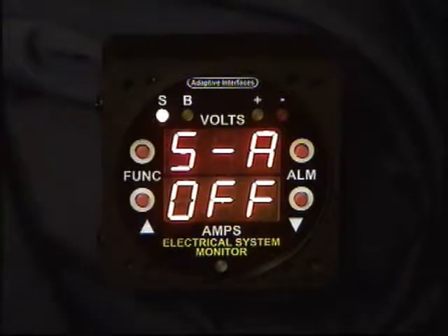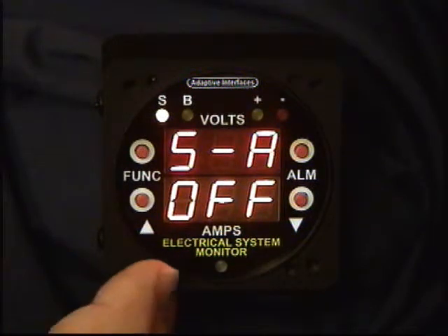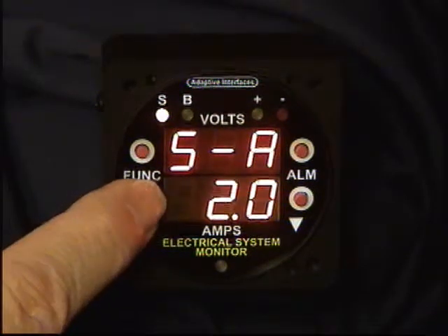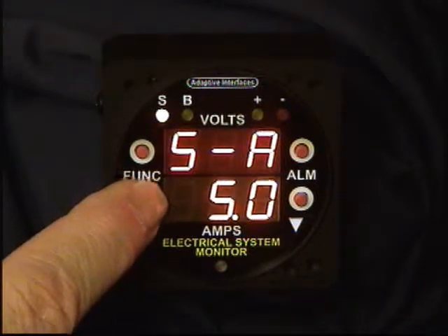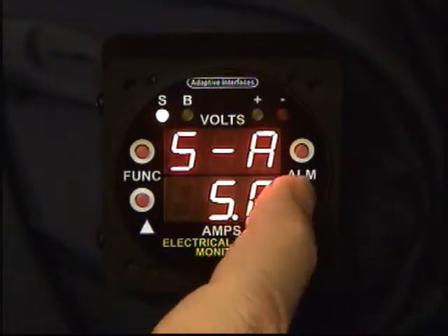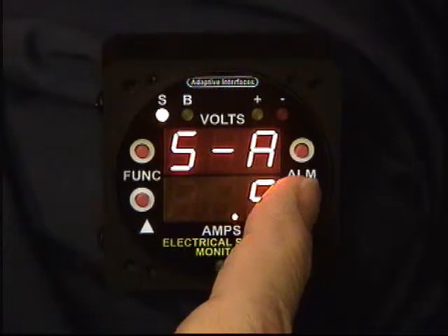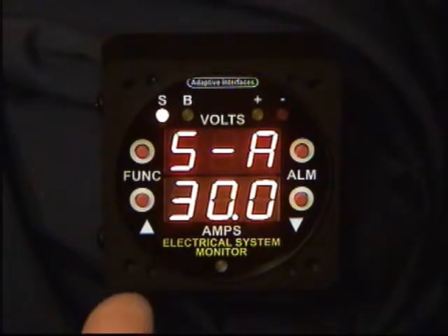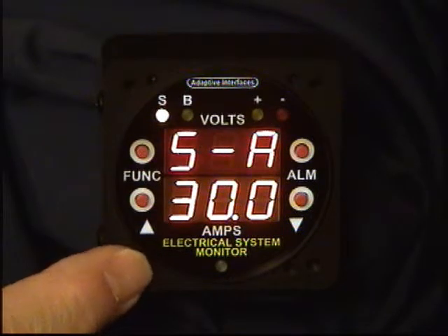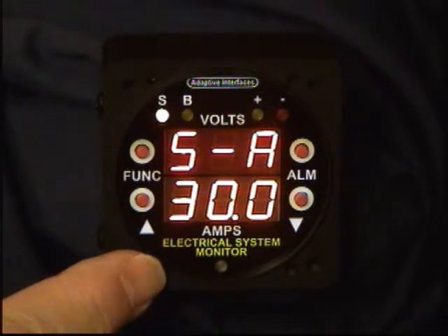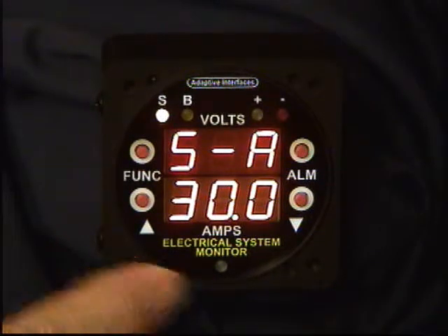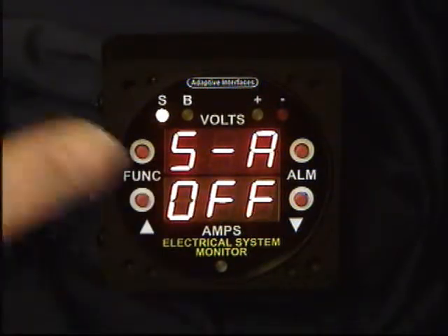The next function is a current alarm level for the system current sensor. Right now it's turned off, but it can be selected in half amp increments. If we go back down through the functions, it can go all the way from 0 to 30 amperes. In this case, if the system current exceeds the value entered as the alarm value, the instrument will go into an overcurrent alarm situation. We'll go ahead and just leave it off.